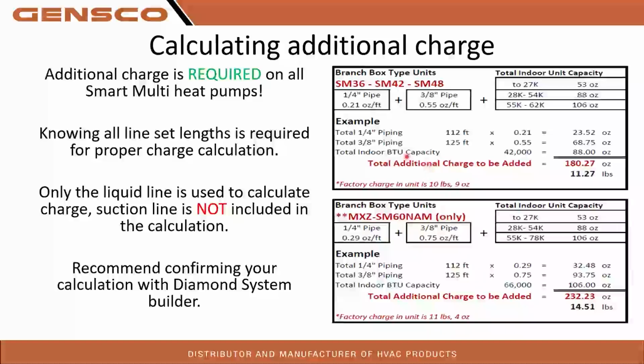So you'll notice the charge calculations right here are different between the SM36-48 and the SM60. The SM60 takes a bit more. But again, we'll use the SM60 here as an example. Once you get your system all installed, you're going to need to go through and measure how long your line sets are. You're going to need to look at and separate the 1/4-inch liquid line from your 3/8 liquid line.